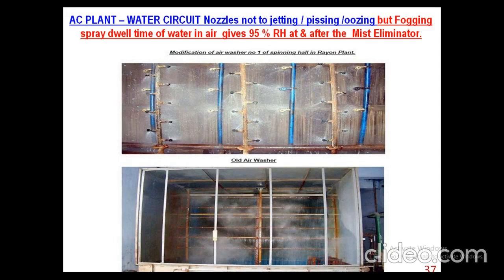The bottom image shows the nozzles operated at 1.5 kg. Say if it is an 80 nozzle line, the first nozzle or the 80th nozzle, every nozzle will get the same pressure and flow. Thanks to the ring main concept, we can just retrofit a T connection on all the vertical riser pipes. You see that the flow and the pressure are available to each and every nozzle. This will reduce the kilowatt consumption of the given pump. You can reduce the pressure of the pump. It will maintain the 95% RH at the mist eliminator, and this is a win-win situation for the mill as such.